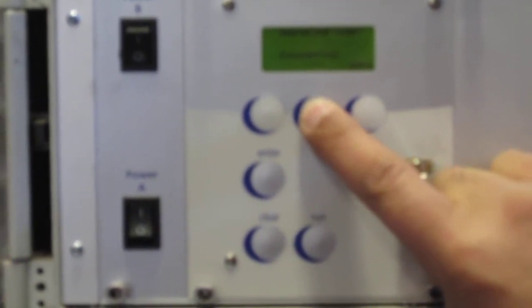A few things you want to look at is operating mode. We have a rod detector on this one. You can do rod detector, you can do exponential, you can do linear. If you do linear, which is a general calibration, usually you have a point detector. You're going to do an open and a close. It's going to ask you for an empty and a full.